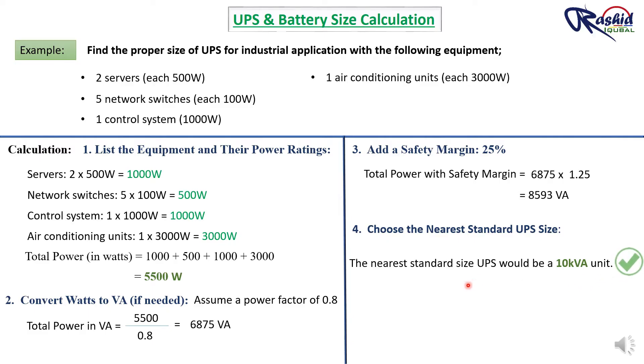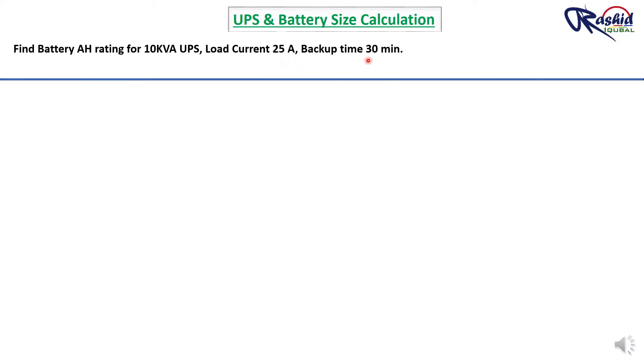Now we will calculate the battery AH rating for the same 10 KVA UPS. The load current is 25 A, the required backup time is 30 minutes, each battery is 12V, and a total of 34 batteries are connected in series, giving a total voltage of 408V.